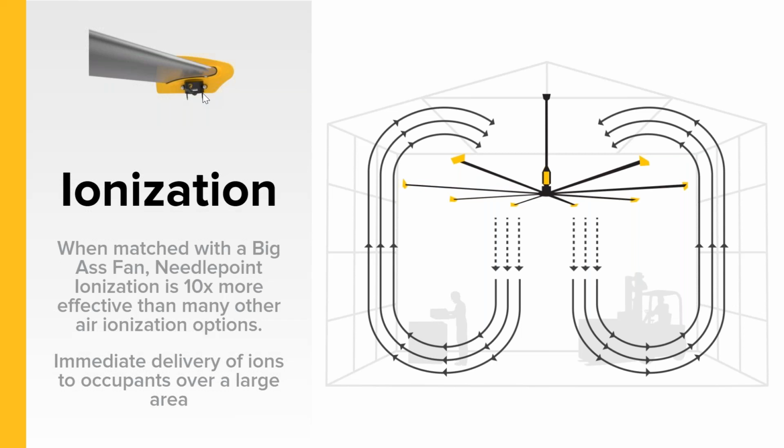The second advantage is air ions only live, quote unquote, for about 30 to 60 seconds. And basically all that is physics. They're highly charged positive and negative particles. And when you put something that has a lot of energy out into the air, it wants to get back to neutral, which means it wants to find something that it can attach to. So within 60 seconds in any indoor environment, those air ions are going to find something to stick to, whether it's a pathogen, a dust mite. By the time it makes it to the floor, it could stick to your shoes, it could stick to the wall, but it's going to find something to stick to in those first 30 to 60 seconds.